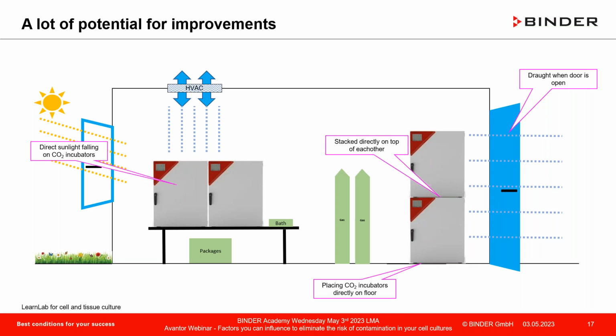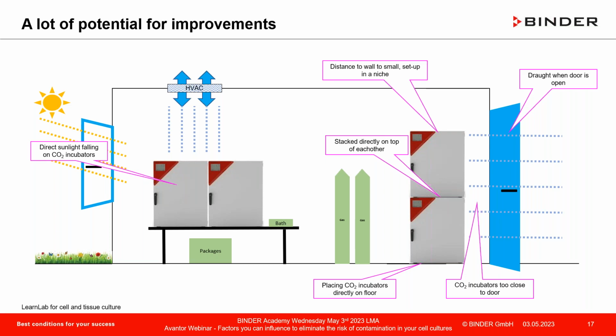Stacking them directly on top of each other is also something you should consider as not being very, very good. Potential for improvements because the temperature, if for example the lower one would be conducting a 180 degrees C hot air sterilization, which is very much a gold standard nowadays, then that will influence the upper temperature at 37 degrees C. And that's something you don't want. Then CO2 incubators are too close to the door. All right, so that's when you move in and move out, close the door quickly because they are more susceptible to any airborne contaminants.